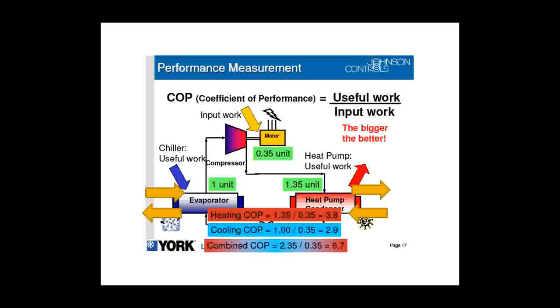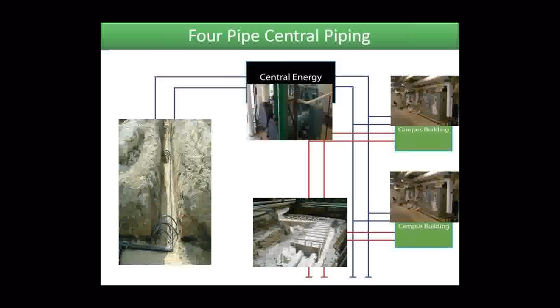On the left-hand side, you see the borehole field connecting the supply and return line to the central plant where the heat pump chillers are located. We make chilled water and hot water to send to campus to the various buildings where that water is used through a typical air handling unit. And the air handling units in most cases did not change. They remain the same. We just plugged and played.